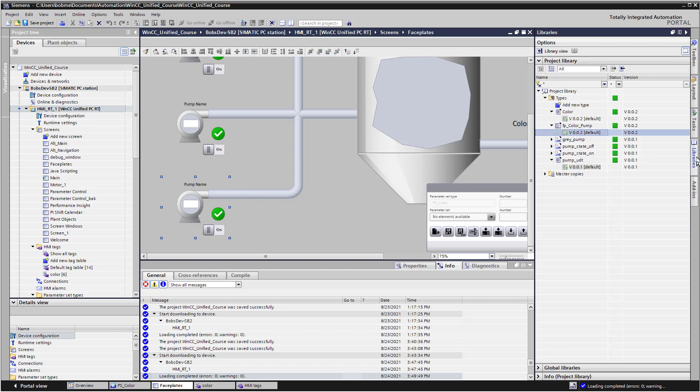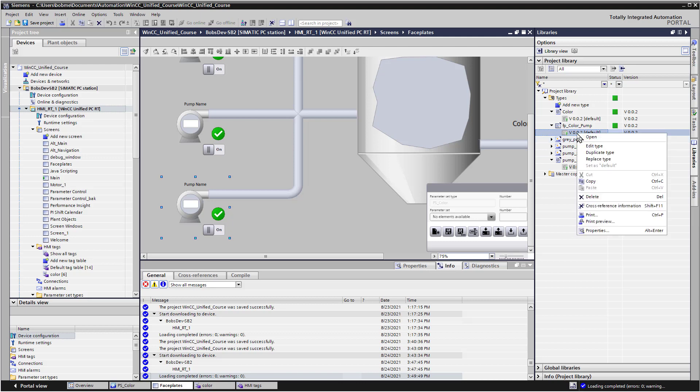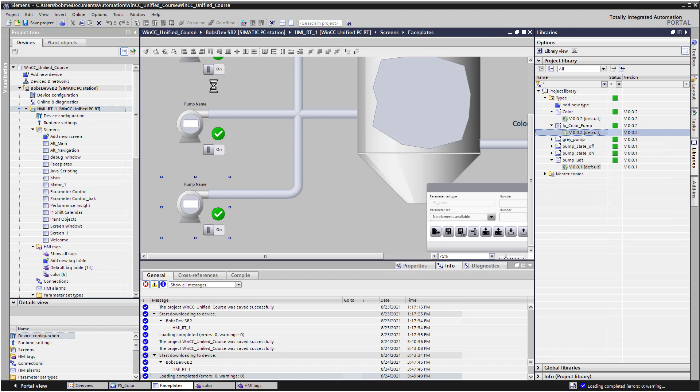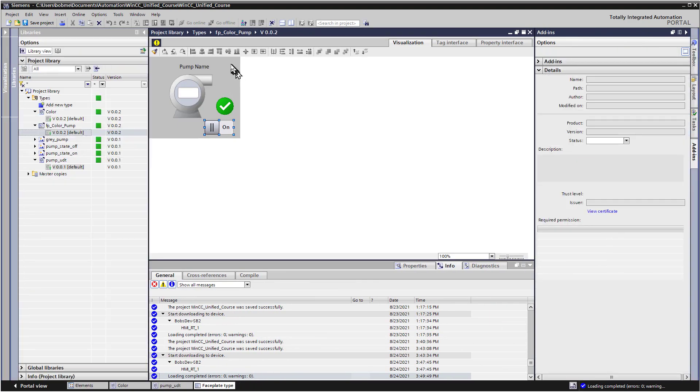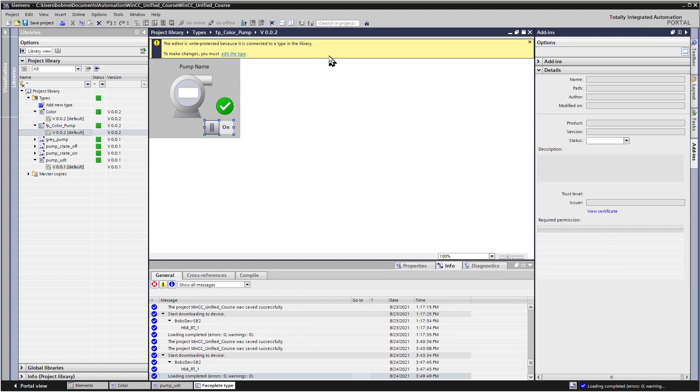And in order to edit the current version of your faceplate, go to libraries, and then you need to right click. Now if you open, that's just looking at it, but it's in read only. And so if you go this route, then it'll tell you in order to make changes you have to edit the type. So we can click edit the type.